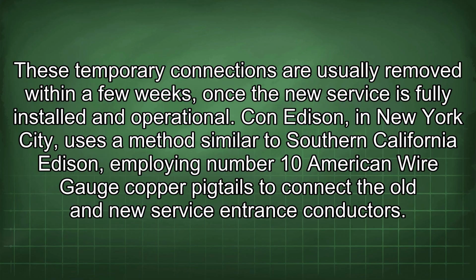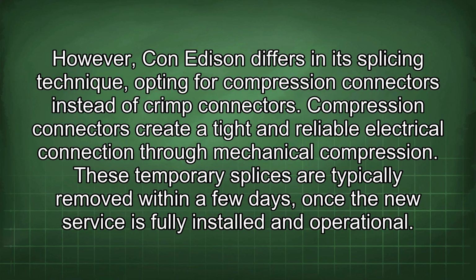Con Edison in New York City uses a method similar to Southern California Edison, employing number 10 American wire gauge copper pigtails to connect the old and new service entrance conductors. However, Con Edison differs in its splicing technique, opting for compression connectors instead of crimp connectors. Compression connectors create a tight and reliable electrical connection through mechanical compression. These temporary splices are typically removed within a few days once the new service is fully installed and operational.